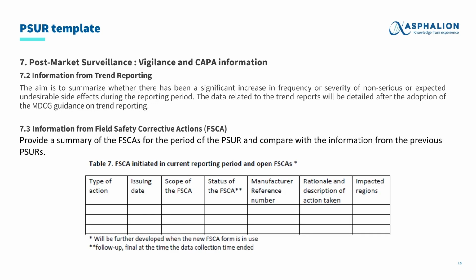Following the trend reporting, the manufacturer should include a section for field safety corrective actions, which, as we know, are all those actions taken by the manufacturer to reduce the risk of death or serious deterioration of patients' health associated with the use of a medical device that is placed on the market. So here the manufacturer will have to list all field safety corrective actions implemented during the reporting period and try to compare this information with that stated in previous PSURs. Here again, you can see a table that can be used to list all these field safety corrective actions.